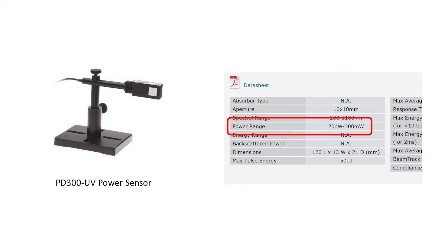A typical laser power sensor can measure powers over many orders of magnitude. For example, the Ophir PD300UV, a photodiode-based sensor for UV and visible wavelength beams, can measure powers from as low as 20 picowatts up to 300 milliwatts. However, if we consider the electronics inside the power meter, one stage of amplification will typically have a dynamic range of maybe several tens to one.